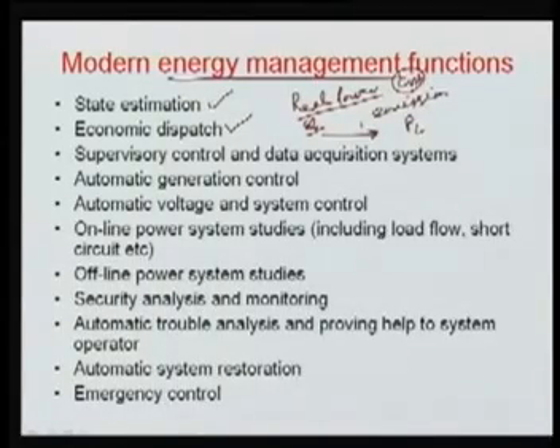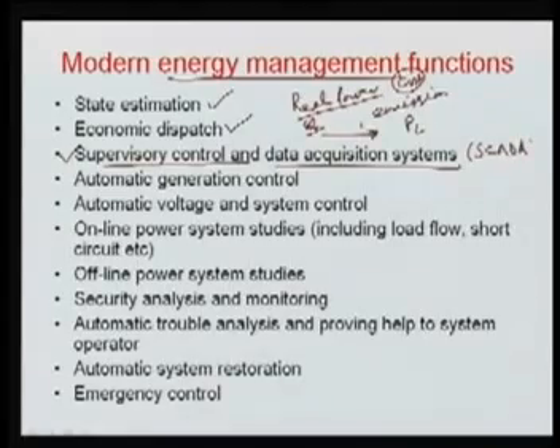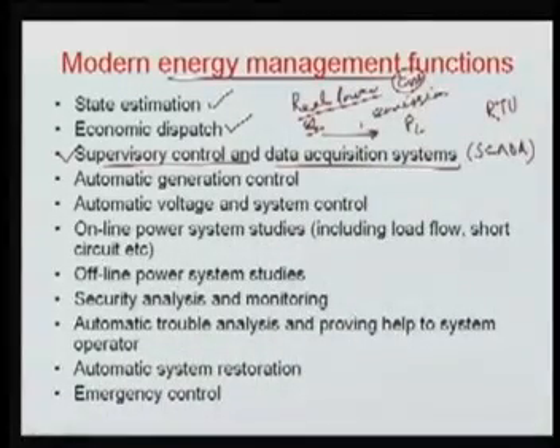Another function we require is the supervisory control and data acquisition system, also known as SCADA, which is very important. SCADA is the supervisory control as well as the data acquisition system. We have to get the data from the field, from the various elements of the power system spread all over the geographical area. We measure those data, transmit them to the energy control center where we can process them, and from there we can go for supervisory control. Any measuring unit like an RTU, a remote terminal unit, measures the data. At the same time, it can also do some supervisory control, and it can send other information to the energy management function.